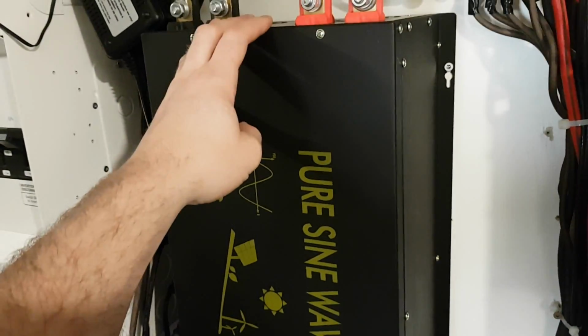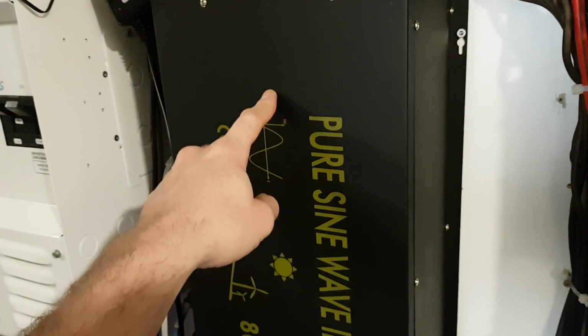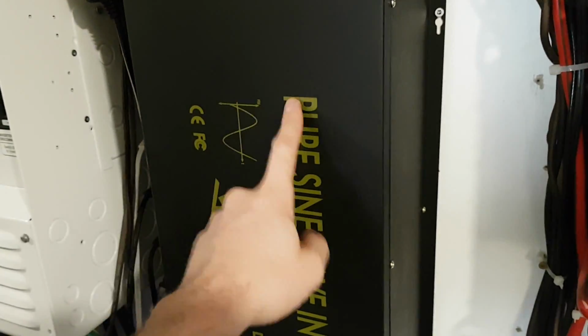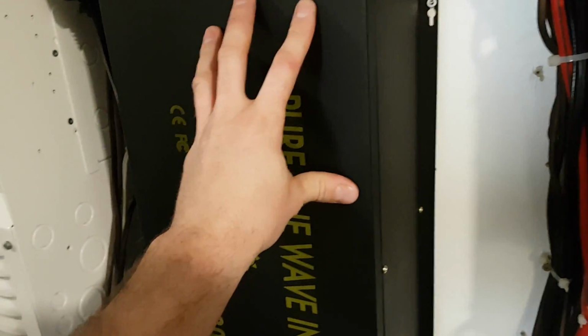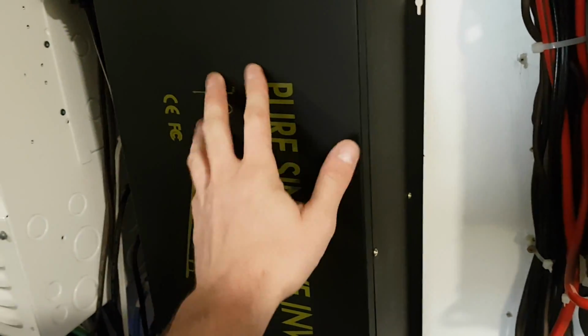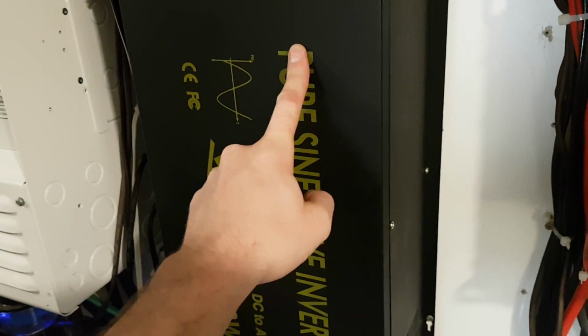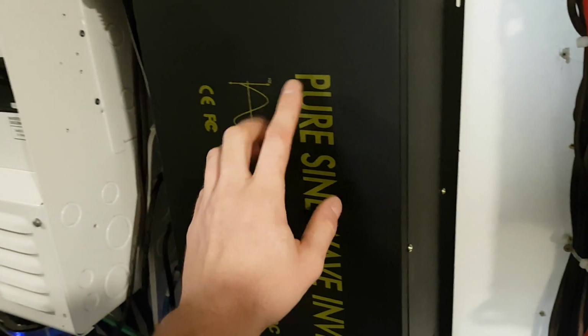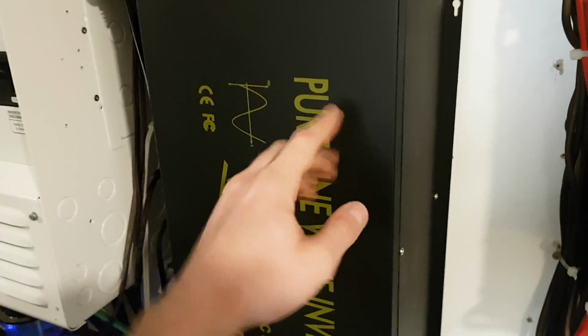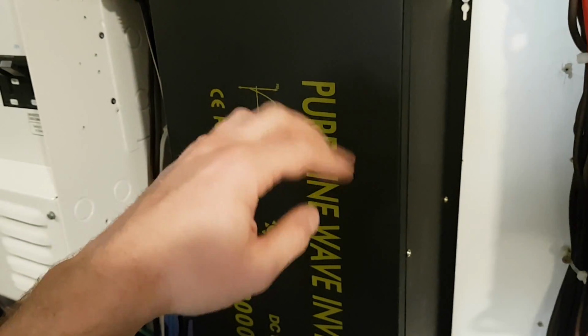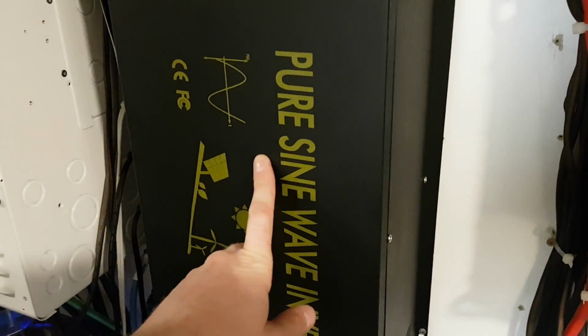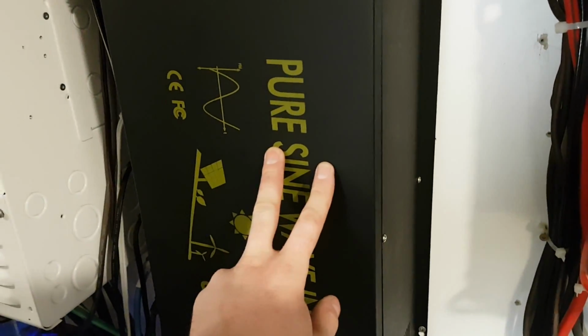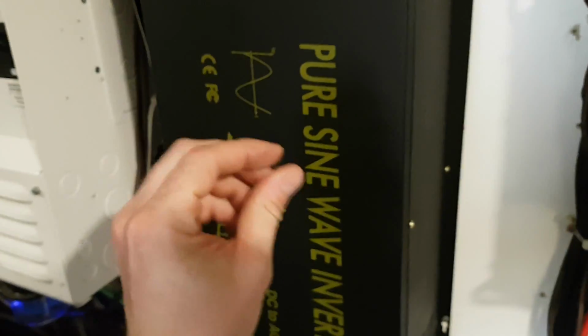I've overloaded it at least 5 or 6 times now, and that was due to me playing with the dryer. I have overloaded it once without the dryer, when I had over 3,000 watts running and my well pump kicked in, which has a wicked surge. That's the only thing that makes this inverter droop a little in voltage and the lights dim, which is crazy because nothing else does that. Not even the furnace, and the central vac barely does it, just a tiny bit.